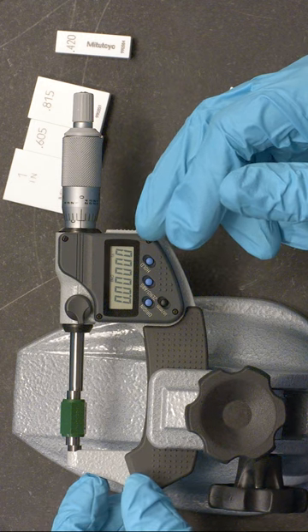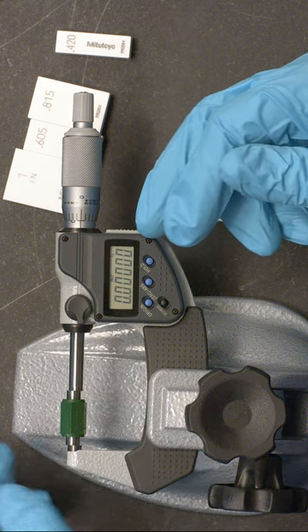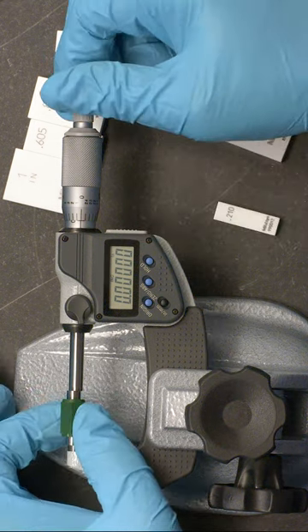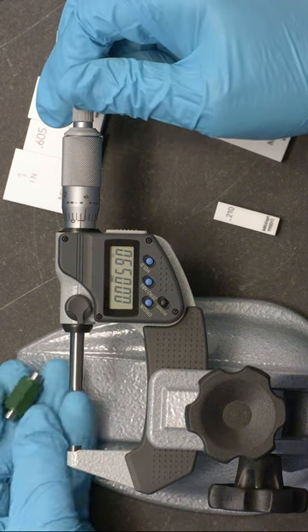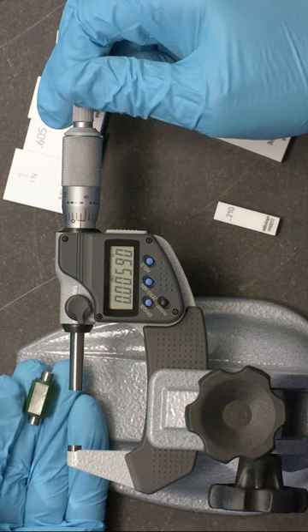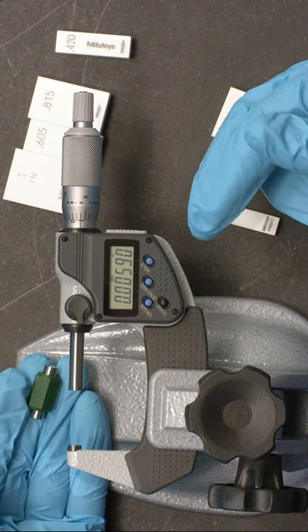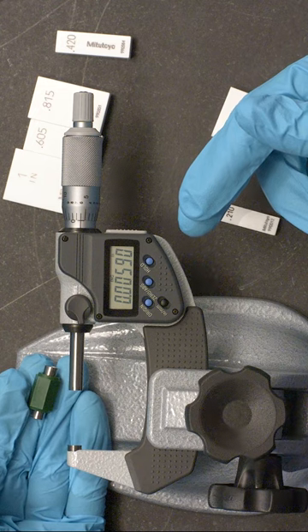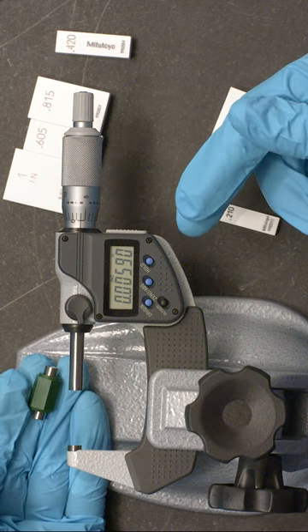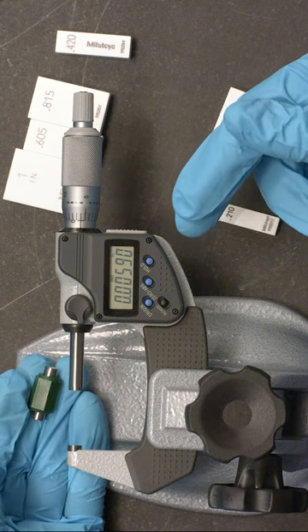So let's cover that. Larger micrometers generally come with micrometer standards, such as this. These standards are useful for the shop floor setting of the zero by the user, but they are not recommended for the calibration of the micrometer.